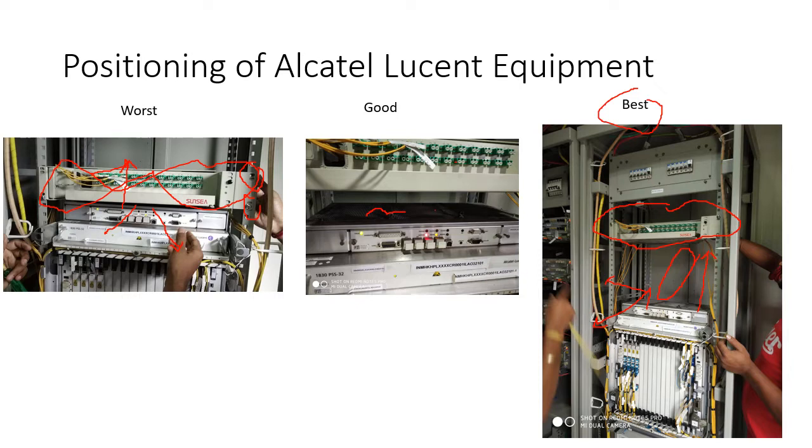So this is another rack, and this right hand side is having a suction. This rack was sucking this hot air and creating a problem for this router, that we will see in the upcoming slides.